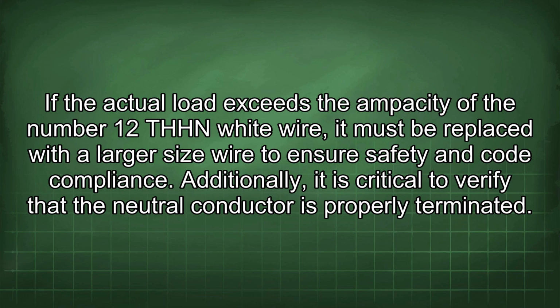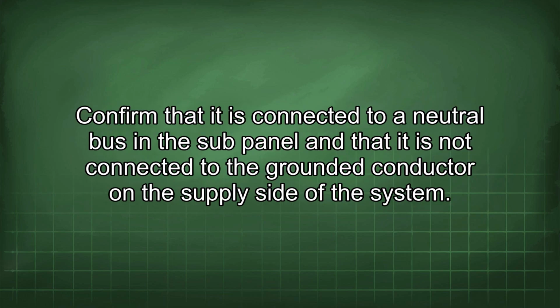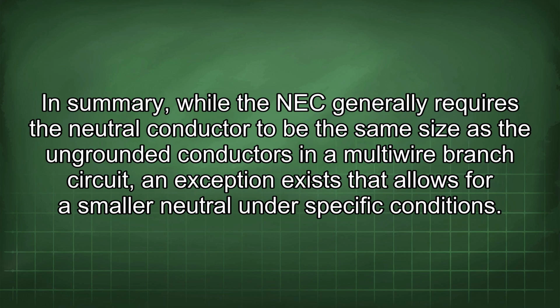Additionally, it is critical to verify that the neutral conductor is properly terminated. Confirm that it is connected to a neutral bus in the sub panel and that it is not connected to the grounded conductor on the supply side of the system. In summary, while the NEC generally requires the neutral conductor to be the same size as the ungrounded conductors in a multi-wire branch circuit, an exception exists that allows for a smaller neutral under specific conditions.